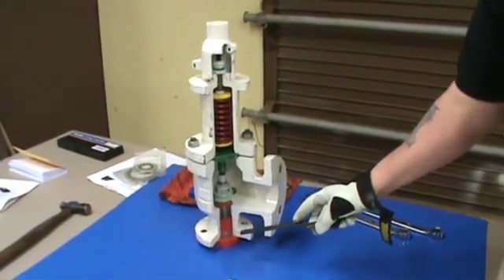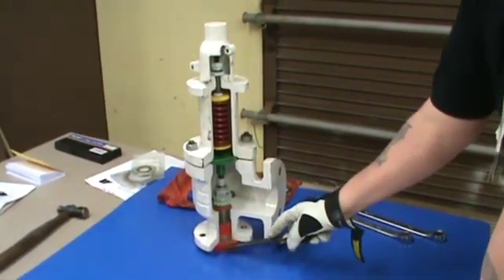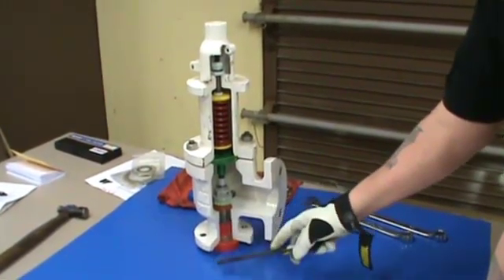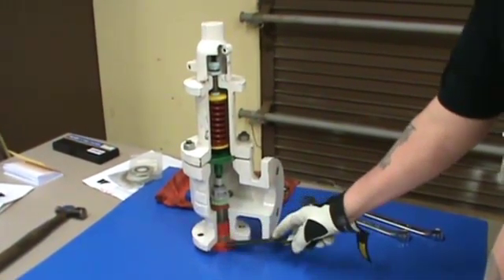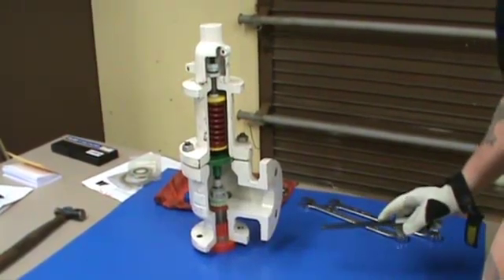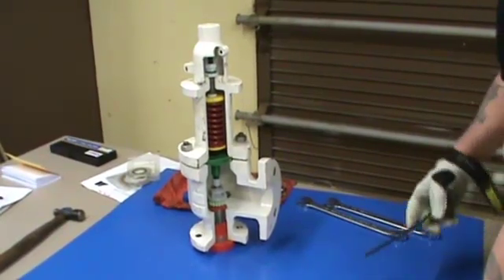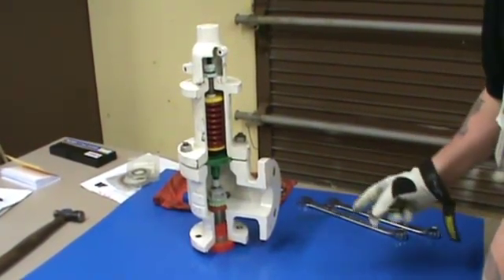Some other things you must always realize about a relief valve. The inlet which is referred to where the pressure comes in through the nozzle will always be smaller than the outlet discharge. That is so the pressure can bleed off faster controlling the problem and reseat.